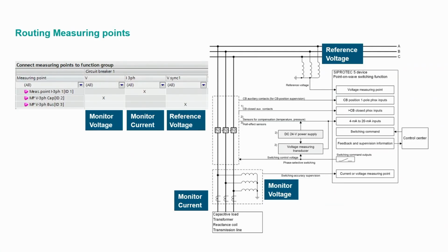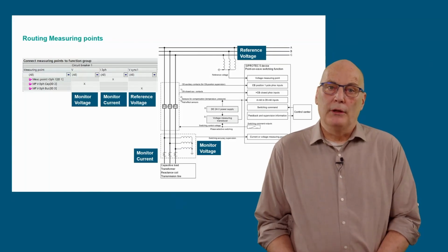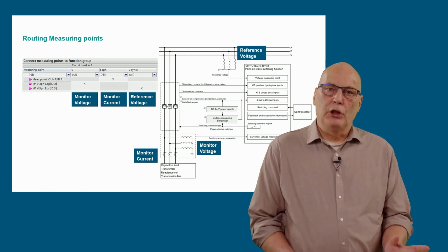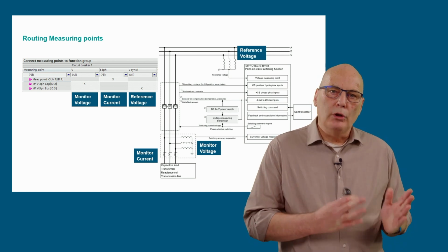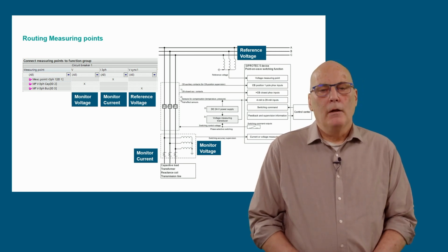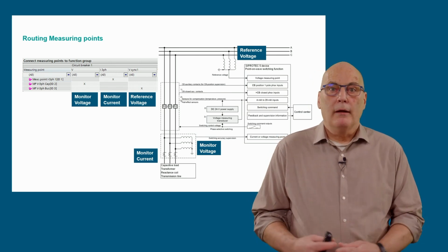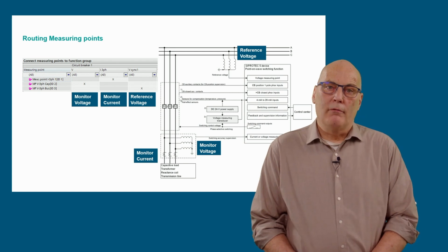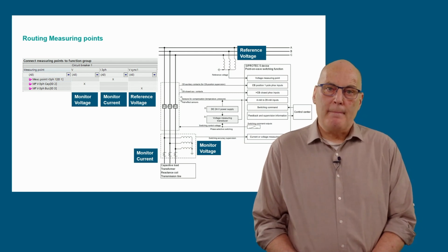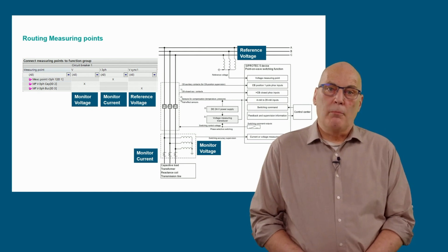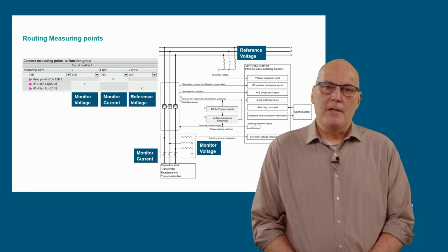The current and voltage routing: the standard SIPROTEC 5 procedure is to make the interface to measuring points at the function group level, so that all functions within the function group have access to these measured values. For the point-on-wave function, the reference voltage at the top is the VSync 1 voltage. The corresponding X must be applied as shown, so that the bus side voltage is routed to VSync 1. The load side current for monitoring and/or voltage are the normal current and voltage measuring points of the function group circuit breaker. These are also selected with X in the corresponding position as shown in the left side.